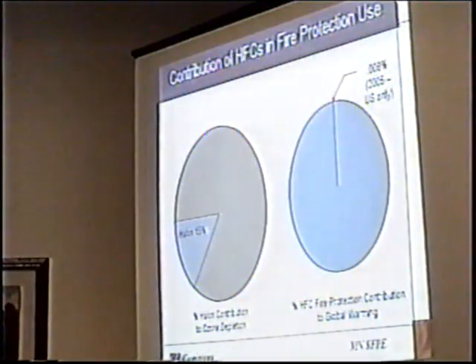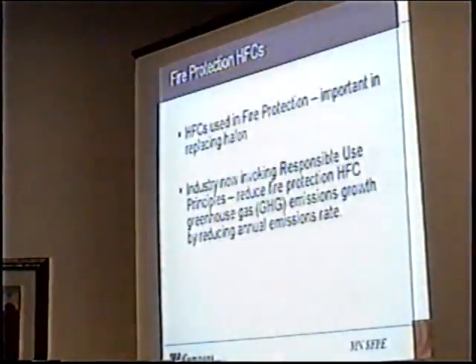But you look at, what's the contribution of HFCs in fire protection units? If you look at the U.S. in 2005, it's only 0.008%. What's the big deal about that? Why is this considered a problem? Why should it be a problem? It's essentially non-emissive. You just said yourself, 95% of the Halon is still in the can. So why would this be a problem?